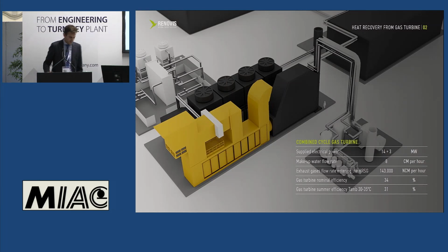In this first slide, and in the next one, we can see the current layout of the turbogas plant. In particular, we can see the gas flow available downstream of the steam generator and its temperature, that is more or less 170 Celsius degrees. This combined cycle plant can deliver an electrical power of 17 megawatts and produce approximately 24 tons per hour of steam, of which approximately 1/3 is made up of make-up water.